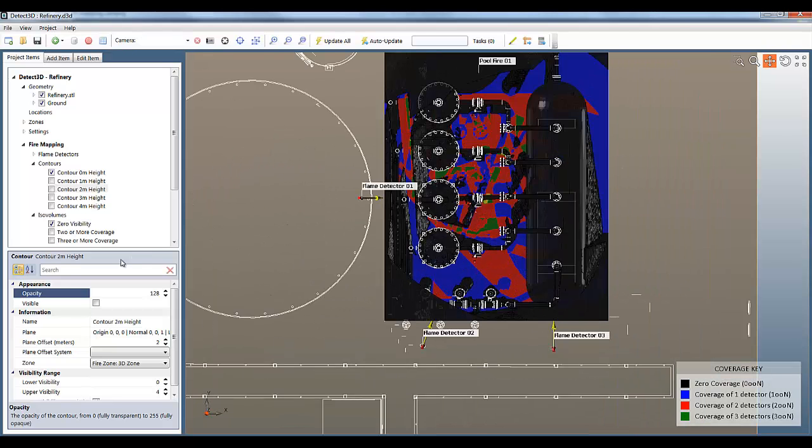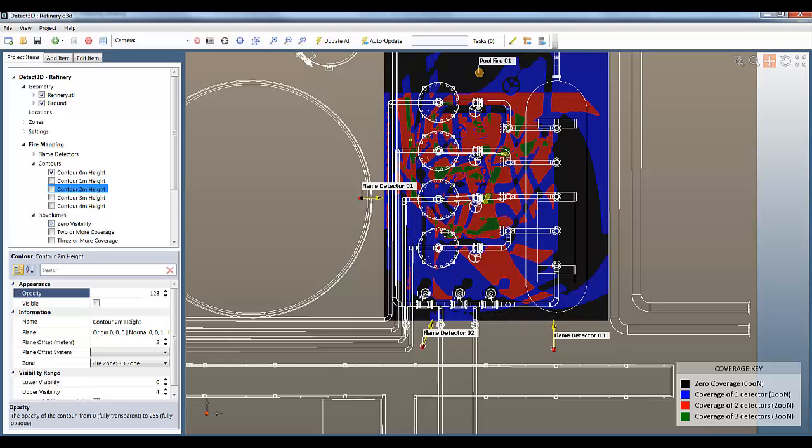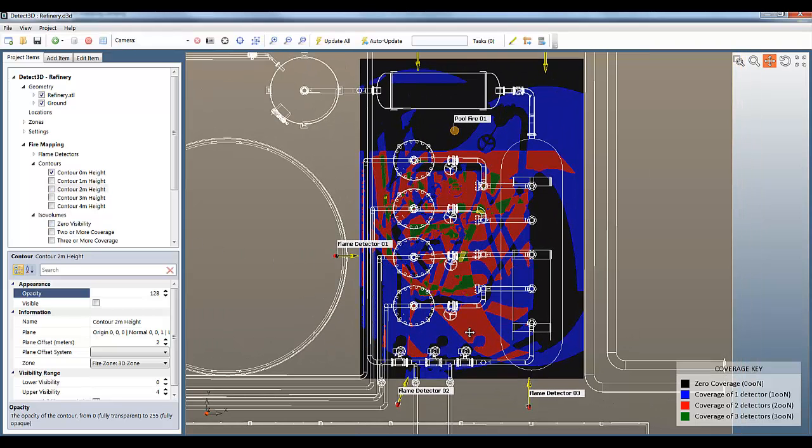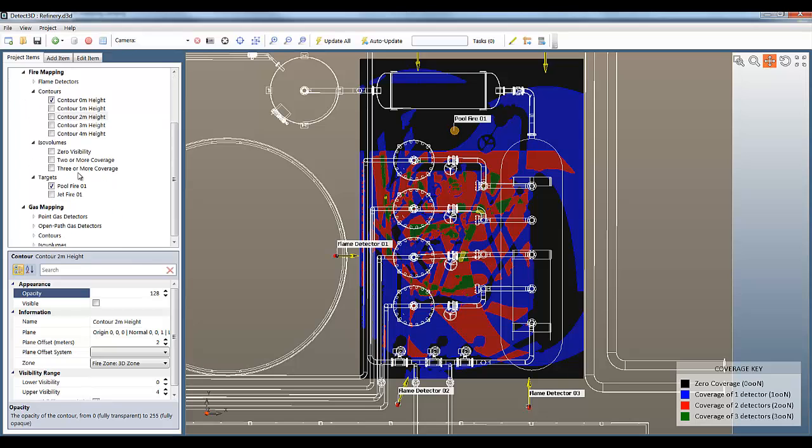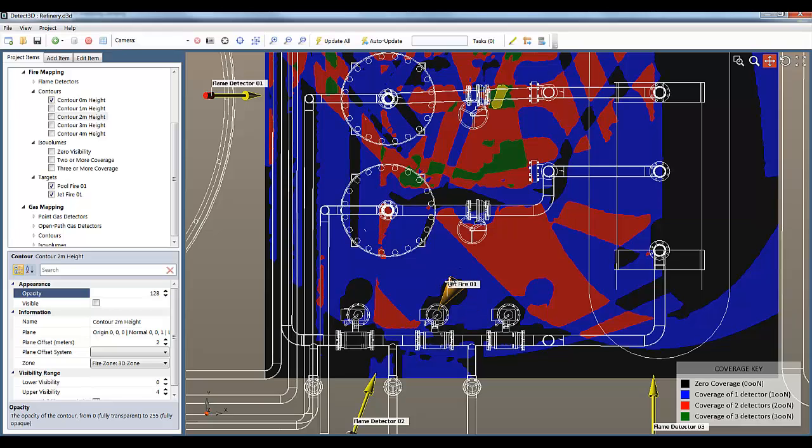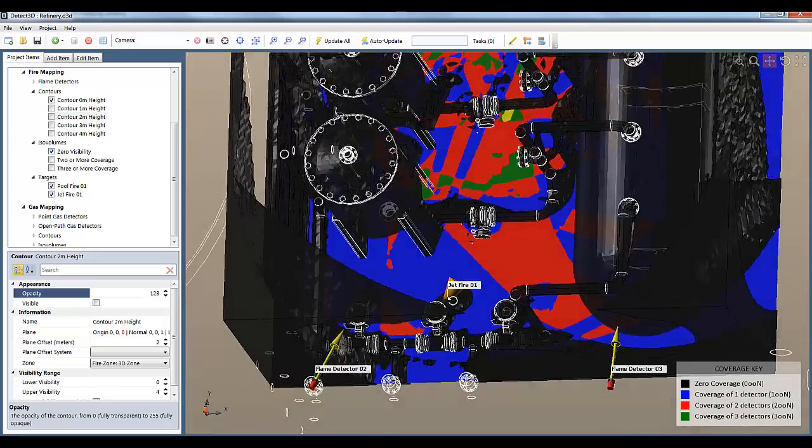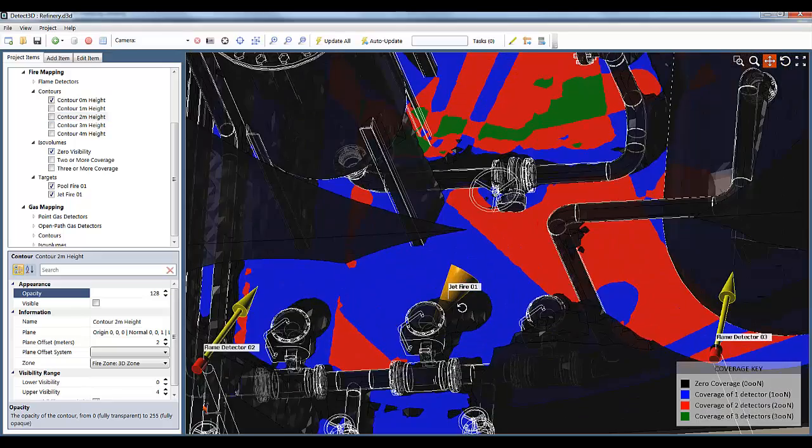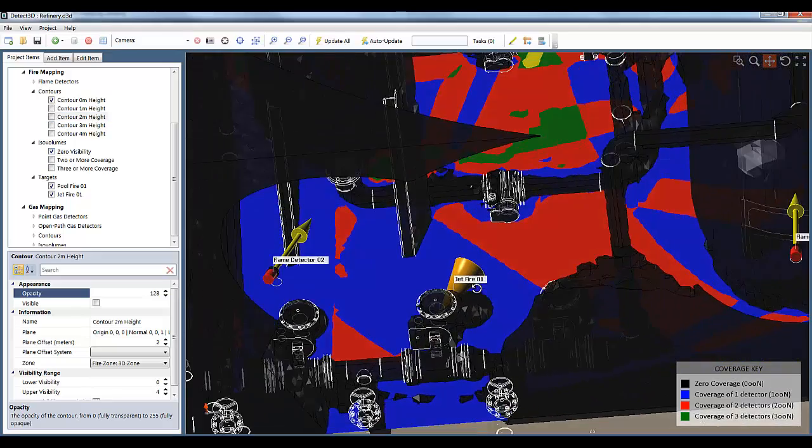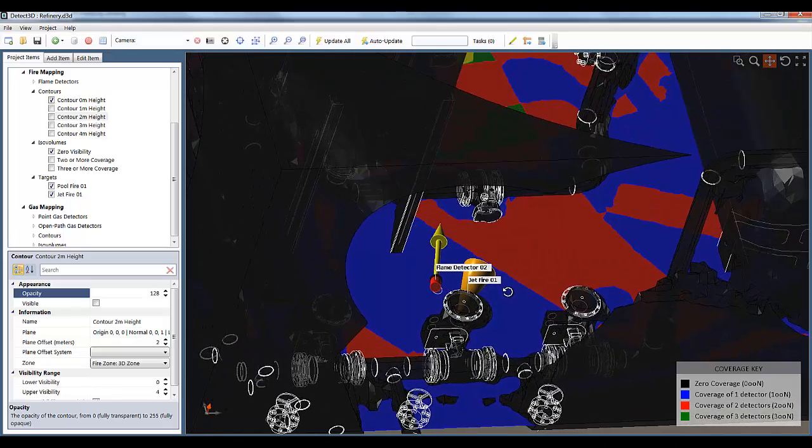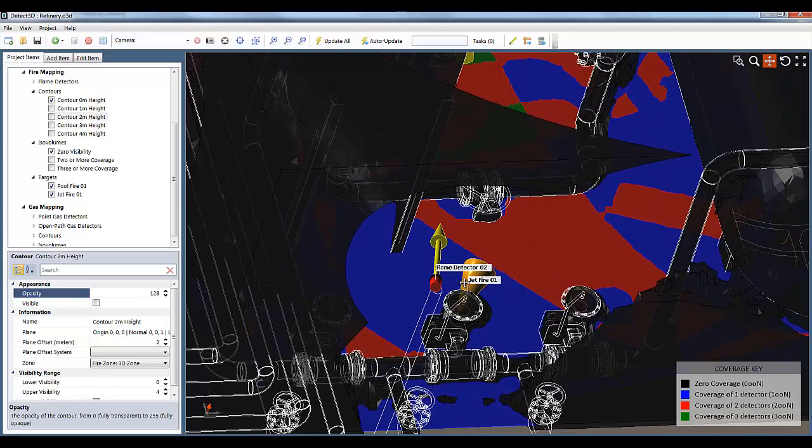The coverage at ground level may have been the obvious choice for a pool fire, but typically you also have to look at jet fires. I've got a jet fire target defined here in orange. Again, the question is how many detectors is that jet fire visible to? On the ground level contour it shows zero, and only in 3D can I see that it is in fact visible to one of the flame detectors. I can line them up here and it's perfectly clear, but the ground level contour showed it wasn't visible to any.